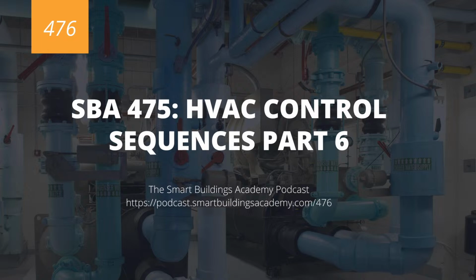Now, with cooling towers, I guess there are three ways we could remove condenser water, cooling towers being the main one. Of those cooling towers, the two ways we can do it are flow through or flow over. Flow through is, like I just said, where the airflow comes across the surface of the water as it flows through the tower. Flow over is where you have a valve that opens up and allows the water to flow from the top of the tower, either dripping down or spraying down. It just depends on the structure, and the fan will once again use the evaporative effect.